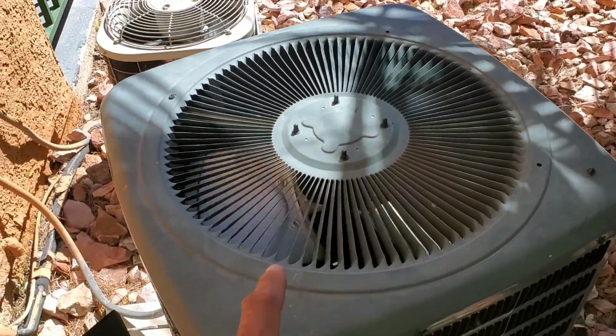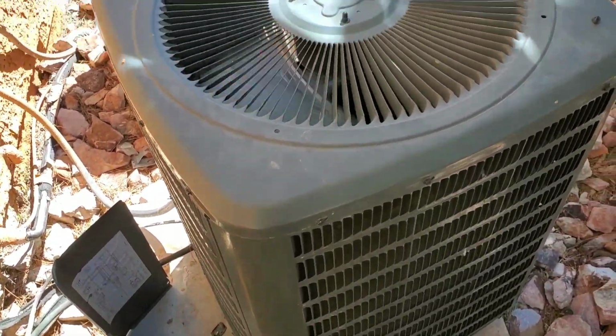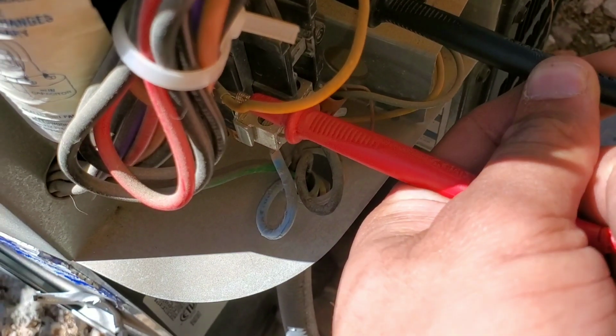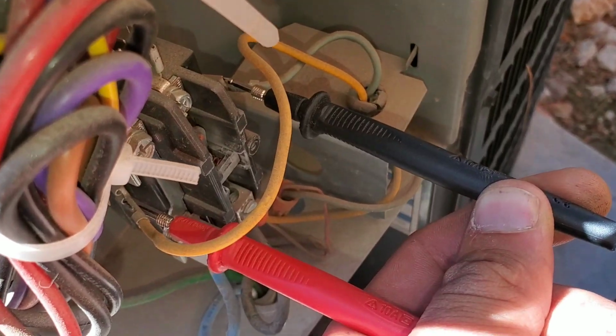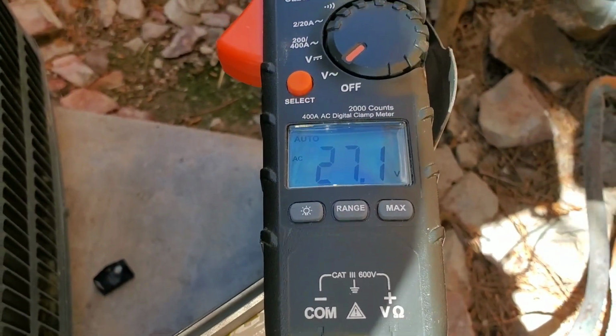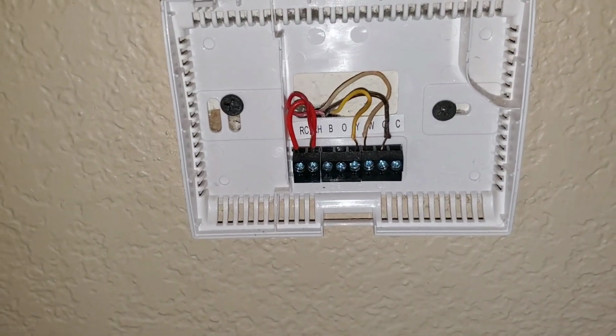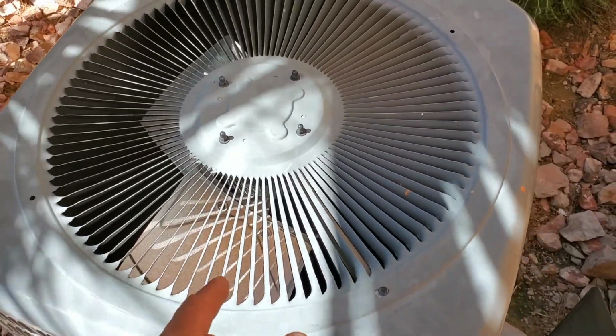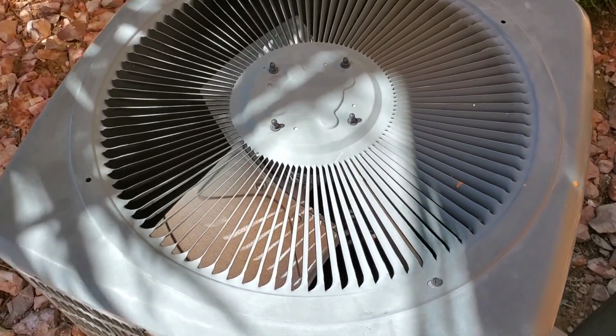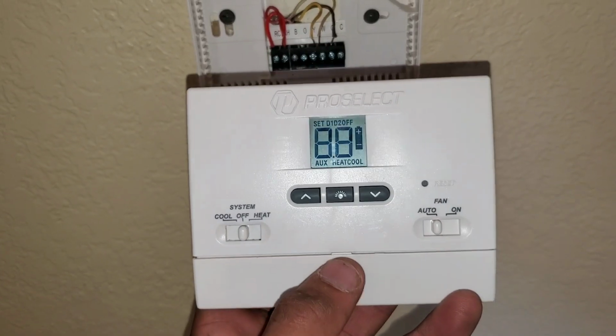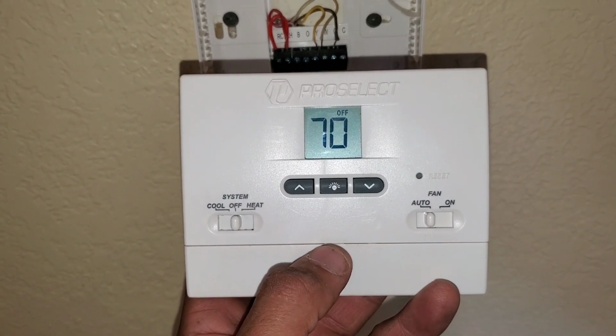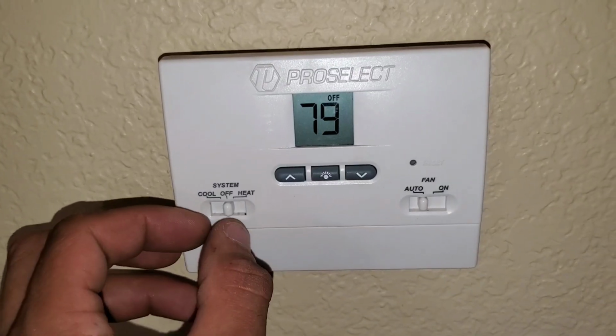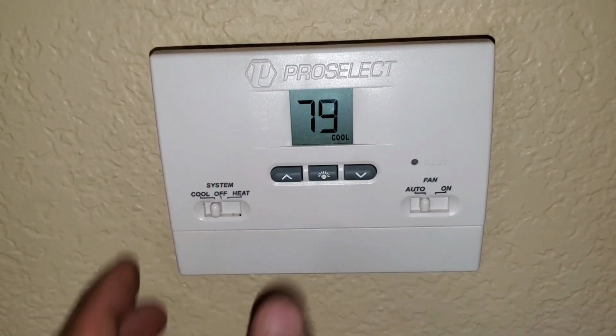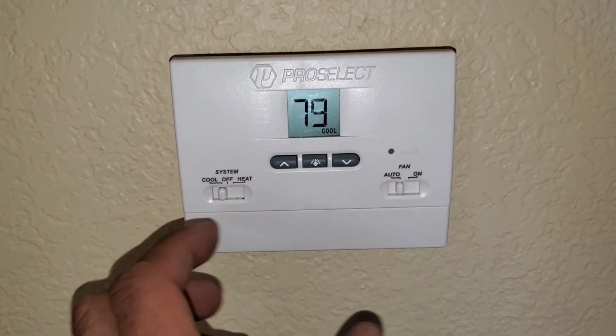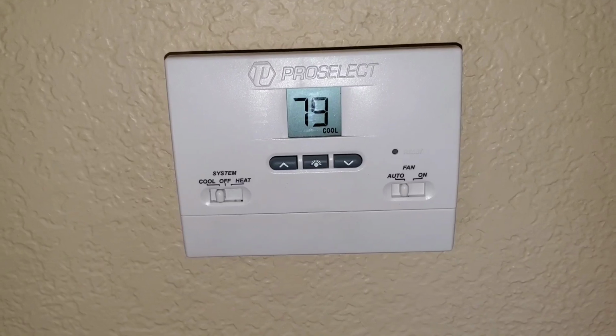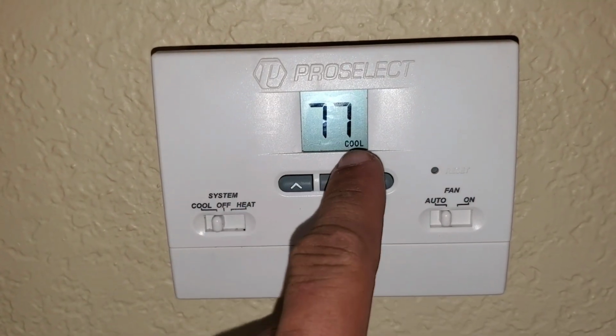So you can see here that I do have power going to my condensing unit. Here I have my multimeter set to volt AC, and I'm just checking my low voltage. And you can see here that I do have 24 volts. We're gonna remove our jumper. Because I removed my jumper, I no longer have 24 volts engaging my contactor. At this point, you're gonna wanna replace your thermostat. Set your thermostat to cool, auto, drop the ambient. Once you install your new thermostat, these do come with a delay, so you may have to wait 2 minutes before the system engages. So here, the thermostat is calling for cool.